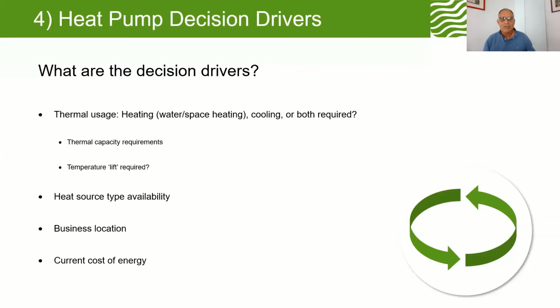If you're in a factory and you have steam being given off - lunchtime today we're talking to an installation where they have a flame next door to their heat pump that burns 24/7 at 700 degrees, 2 meters high. So you can take heat from that flame and input it into the heat pump to provide a boost to all the heating across the building.